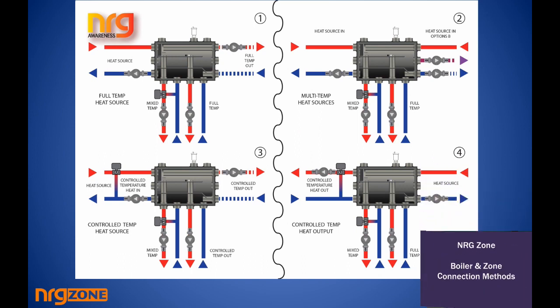Now we'll just have a quick recap on what we were talking about. If your heat source is on the left hand side, you could have a mixing valve and a pump arrangement on A1, A2. You could have full temperature with the pump drawing full temperature water out at the B1 and B2, and you might have full temperature off the right hand side where the flow is being taken through this pipe in reverse order, what we're talking about, and the return coming into the bottom chamber taken back by the pump. So you could have heat source on the left with multiple temperatures.